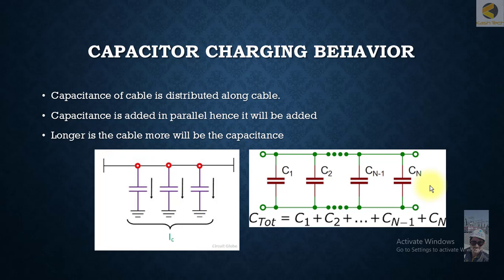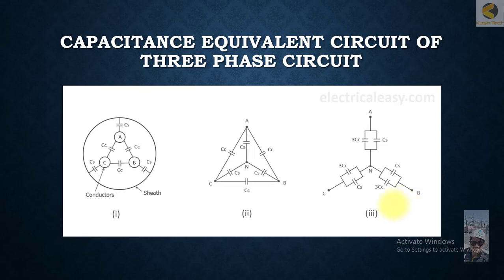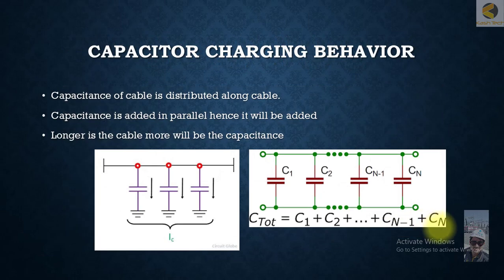If it takes more time to charge, you cannot do spot testing. You have to do time-based testing — apply the voltage for a certain time, let the reading settle, and in this way you will be able to get the correct reading.